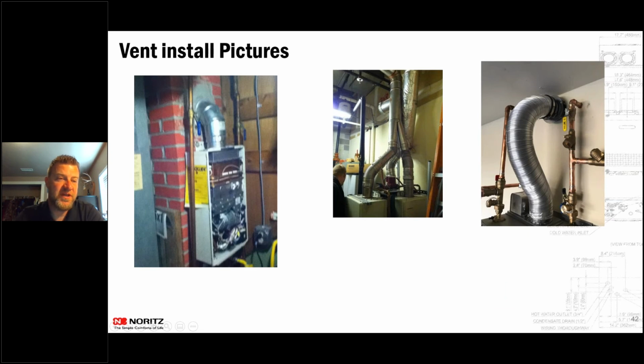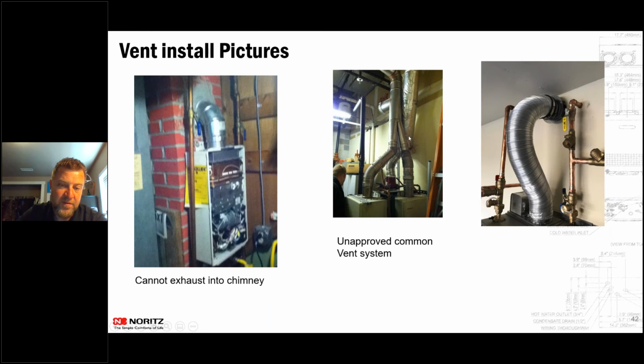So here's a few pictures of some vent installs that are completely wrong. This one over here on the left side, that's actually B-vent that they connected to the top of this unit and then just kicked that 90 into a chimney. That is not an approved install. This one here in the middle, they actually have 3 racks or 3 units that are back to back on this little rack system that they built, and they hooked stainless steel, but then they hooked it into one big giant B-vent. As you can see, it's rusting out all over there from the condensation that's going through there, and they kept getting error codes and they didn't know why.